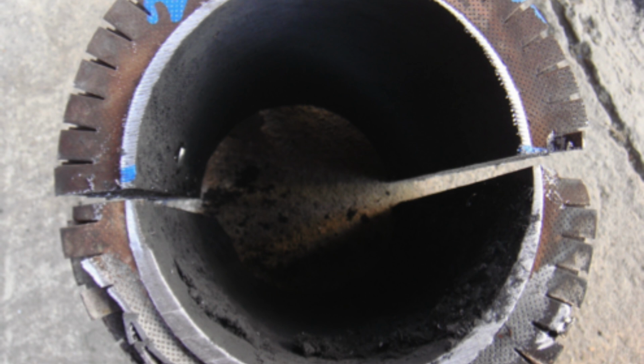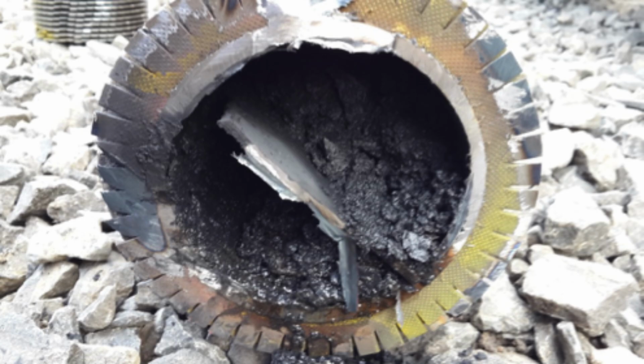You can see all of the damage from the inside, and you can see the top side is very thin and the bottom side is very thick. But definitely it is from inside, from the water side, and therefore it's the water's fault. But what was quite interesting was the amount of corrosion products that was collected at the low flow area. In any case, after a long investigation, what we actually did find was that there was insufficient flow in the tubes, and then you get departure from nucleate boiling and then stratification of the steam.